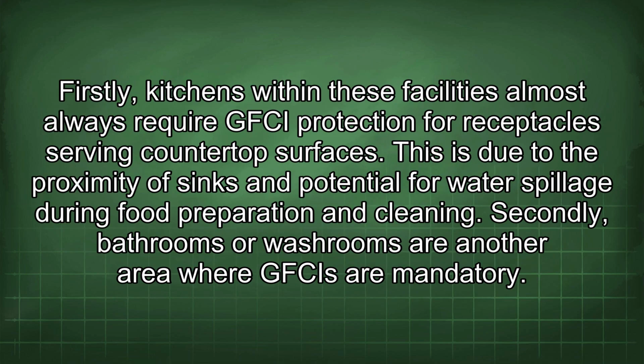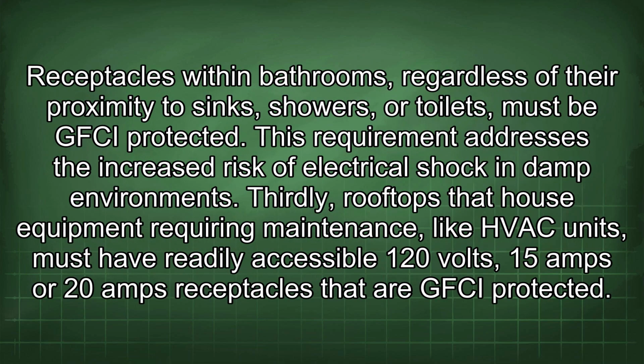Firstly, kitchens within these facilities almost always require GFCI protection for receptacles serving countertop surfaces. This is due to the proximity of sinks and potential for water spillage during food preparation and cleaning. Secondly, bathrooms or washrooms are another area where GFCIs are mandatory. Receptacles within bathrooms, regardless of their proximity to sinks, showers, or toilets, must be GFCI protected. This requirement addresses the increased risk of electrical shock in damp environments.